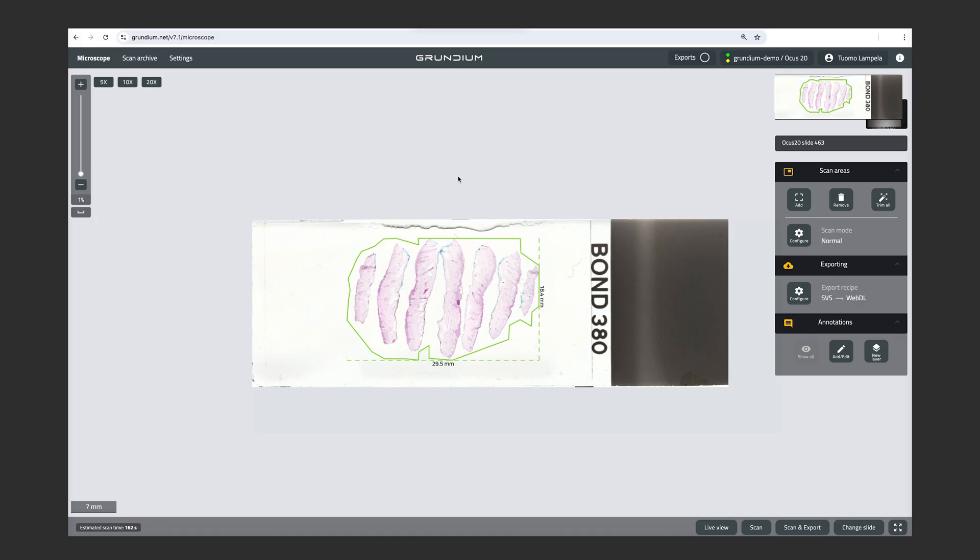After that, the scanner starts taking an overview image of the slide, and that takes around 10 to 15 seconds. And after that, we have an overview image on the screen that we can look at and choose a scan area that we want to scan at full resolution. In the UI here, we have the microscope view, where we are right now.